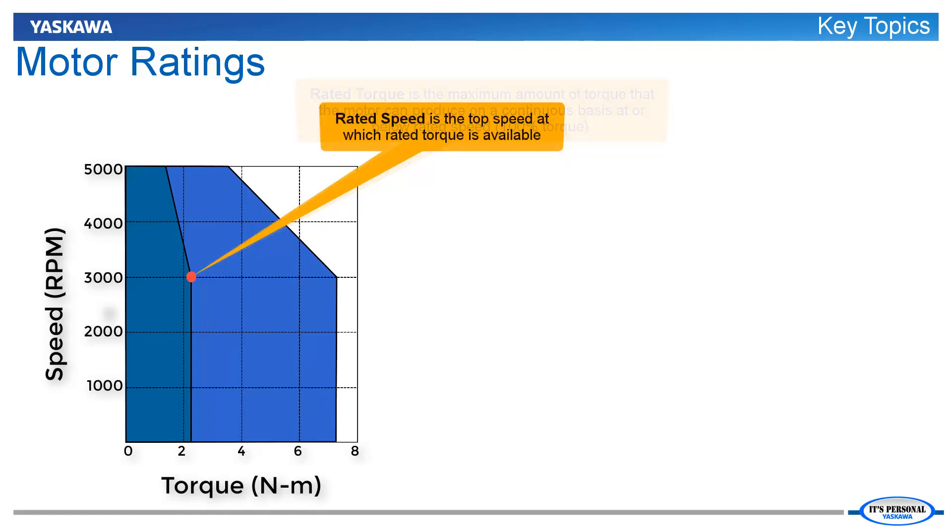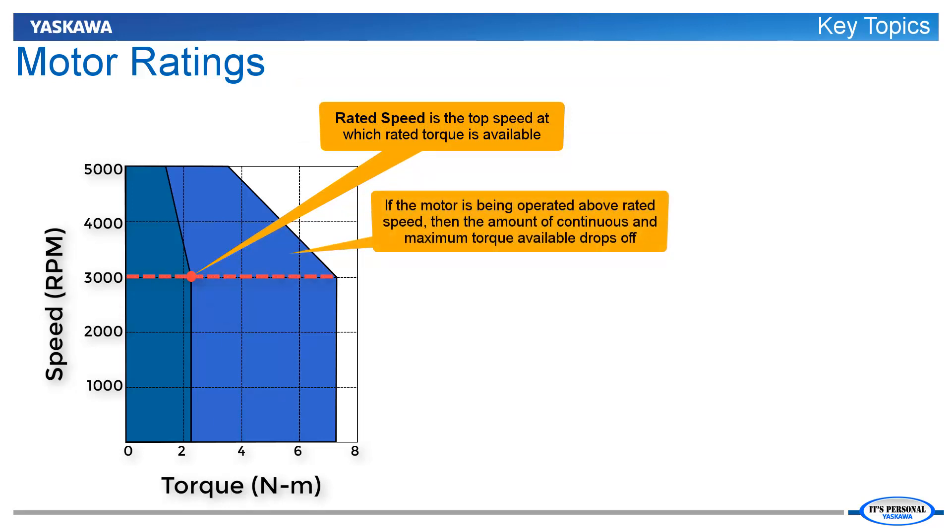Likewise, rated speed is the highest speed at which rated torque is available. The motor can continuously run faster than rated speed, but the torque available drops significantly the faster the motor runs.